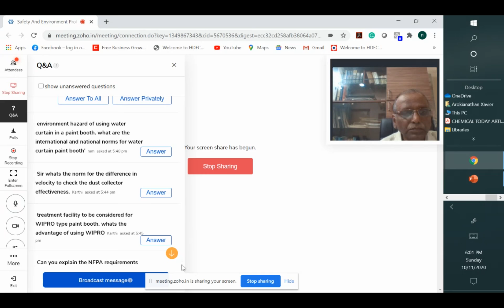Somebody has asked about NFPA standards. Can you explain the NFPA requirement for paint, as we have the paint booth in the middle of the shop floor with all the mixing happening on the first floor? Sir, the NFPA requirement is that the paint booth should have flame-proof fittings inside, so normal electrical connections are not allowed. Any switch or instrument inside the paint booth should be flame-proof. You should also have a CO2 sprinkler system and a sensor to detect any rise in temperature so it can be contained immediately. You can refer to the standards.